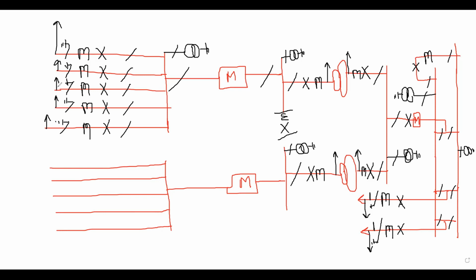Suppose now I want to synchronize the wind turbines to the grid. Now, how to do that? I have to back charge. It means I am taking some power to the generator, up to the WTG, wind turbine generator. So the wind turbine generator will see the reactive power, active power, and based on that, it will generate the power. From then, the wind will generate the power. So first, starting, you have to take the power from the grid to the generator. When you are doing that, the power is coming through this. So you have to know whether the voltage has come up or not. If the voltage has appeared, then you close this breaker. So for the checking, you require a potential transformer here. So I require a potential transformer here.